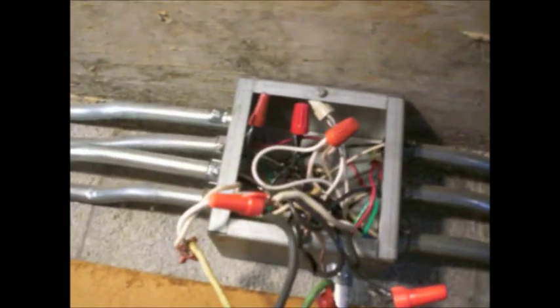Alright boys and girls, I had a duh moment. I went back to my electric panel to check for my 208 volts and I have it. I come here and check and I don't. I went to my junction box just around the corner — I'll show you that — and I hooked up to the wrong leg of something. There we go: 232 volts, up from 208. Right like they said I would. Dum-dum! Here's my junction box — I hooked up to the wrong side of something. It's hard to trace the wires in there; they're all a big mess. Now I'm hooked up properly.